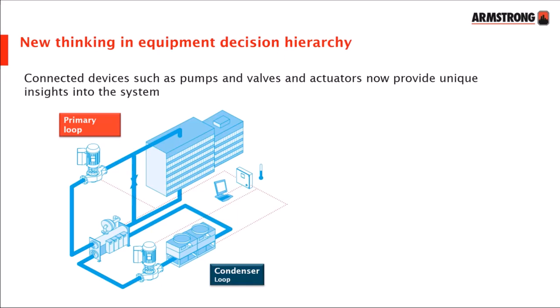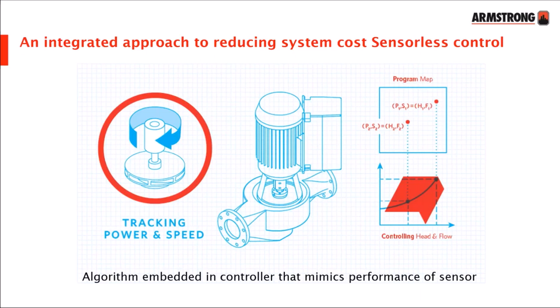So we said we'd look at sensorless. Sensorless control monitors and controls the pump without the need for a physical sensor. So you don't need our pump and a sensor, the pump will do it all. And this simplifies commissioning. It makes it easier to achieve a designed energy performance, which is critical to getting that return on investment you were promised at the start of the project. And it also provides flow measurement without the requirement for a flow meter. So you can see we're reducing down the number of additional components needed over and above the pump.